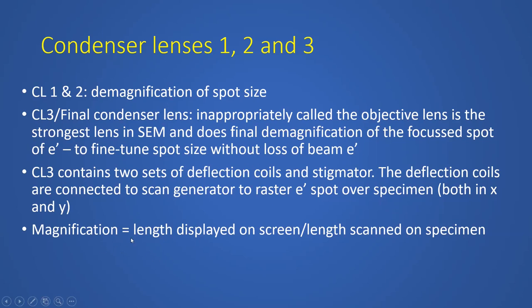And in SEM, the magnification is basically the length displayed on the screen divided by the length scanned on the specimen. So if the length of the object you're looking at on the screen, if you use a ruler, is 10 centimeters, and the length that is scanned on the specimen inside your chamber is 10 millimeters, the magnification will be 10 times. So it's as simple as that. It's the length displayed on the screen divided by the length scanned on the specimen. The length scanned on the specimen is on a much smaller scale, like 10 millimeters, and if the length on the screen is 10 centimeters, the magnification will be 10 times.